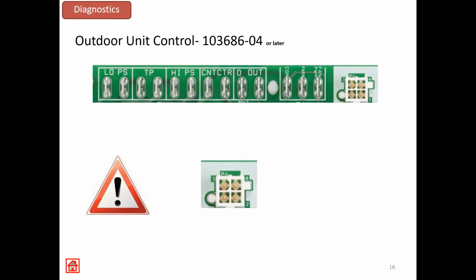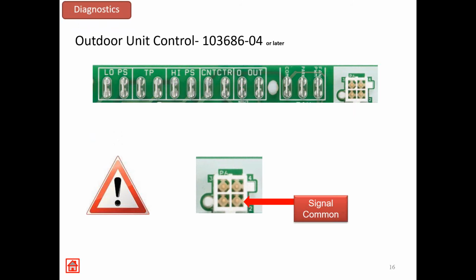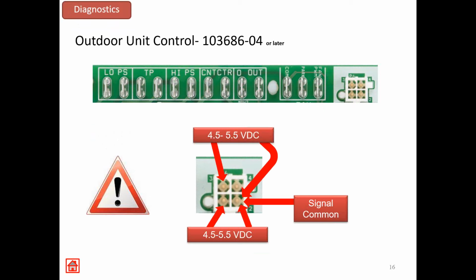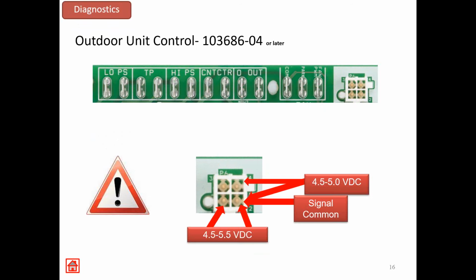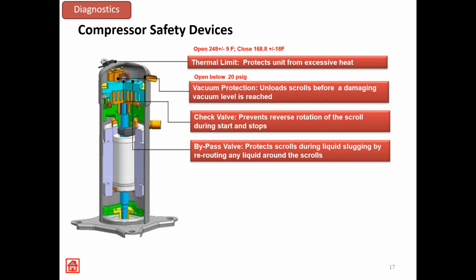All right, we've been talking a little bit about our 3-phase AC compressor that we feed with DC voltage. Pin number 2 is the common signal. Then 1, 3, and 4 are your leads on the compressor, like the common, start, and run you're used to. Those are each fed individually with an equal amount of signal, and it ranges anywhere between 4.5 and 5.5 volts DC. I have seen it a little lower and a hair higher, depending on the load of the house, but it's going to fall right in that area. All 3 of your leads outside of the common signal should read very similar across all 3. This is DC voltage again at this point, so make sure your meters are set to that.